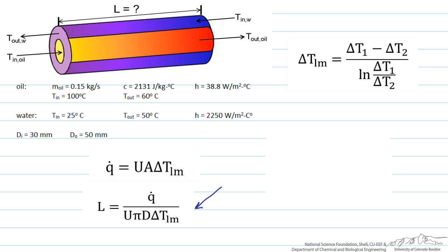Looking at this picture, we can see that our delta T1 is going to equal the temperature of the oil that's entering the system minus the water that's exiting the system. So that means that our delta T1 is going to equal 100 degrees C minus 50 degrees C or 50 degrees.